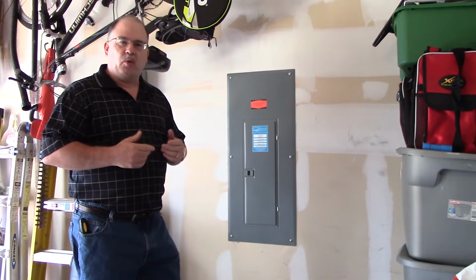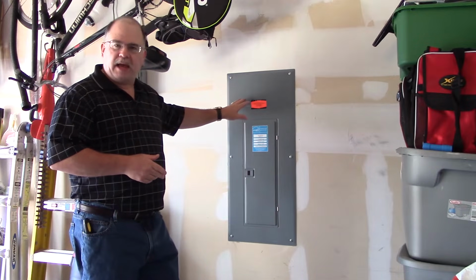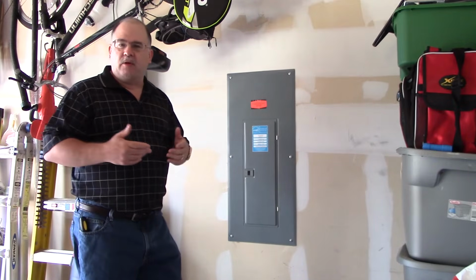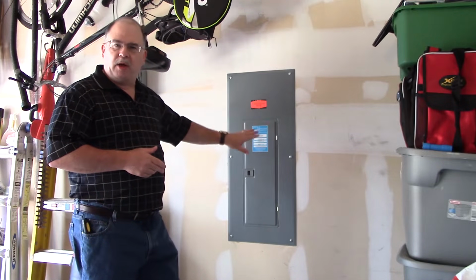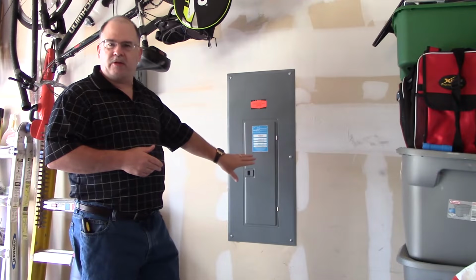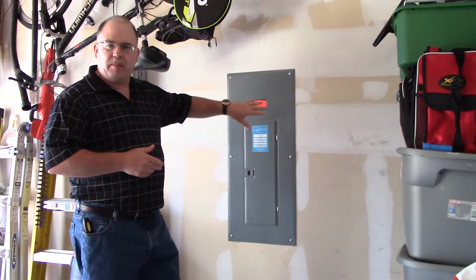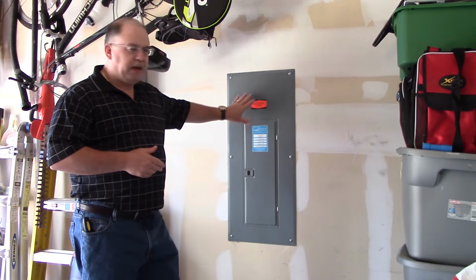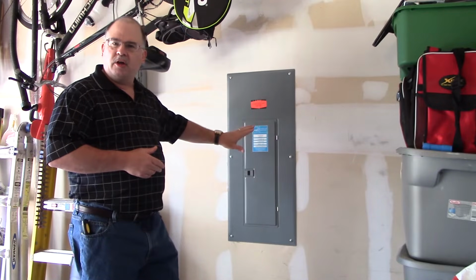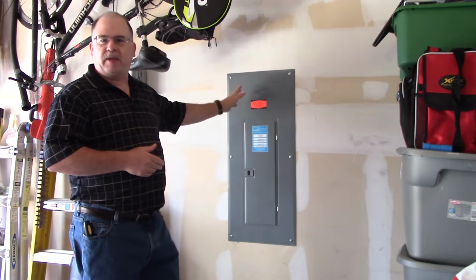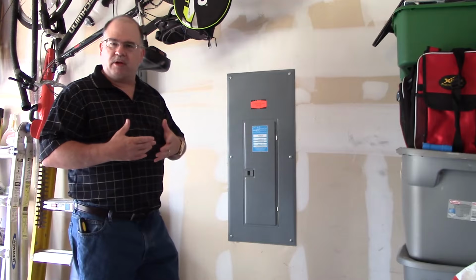On today's episode, we're going to do an inspection of this electrical cabinet inside of a single-family dwelling. We're going to look at the panel board, main breaker, the grounding electrode system, the grounding conductors, the equipment grounding conductors. We're going to look at the panel cover.